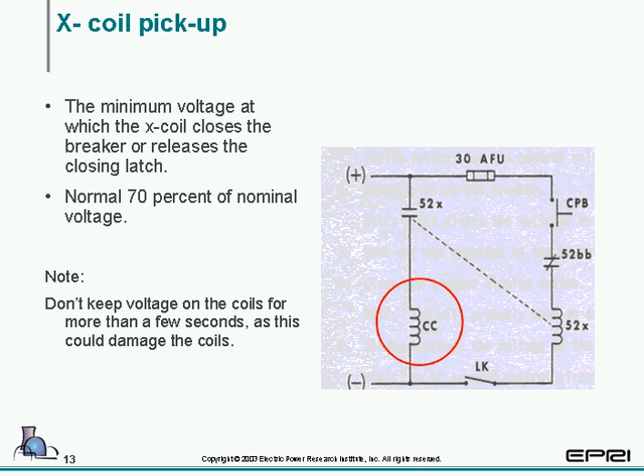And what this basically will do is give you a margin of voltage that you know the piece of equipment will function. So if it functions at 70% of its nominal, you can be pretty well assured that it'll work at its nominal voltage for the life of the time that the breaker is in that cubicle.